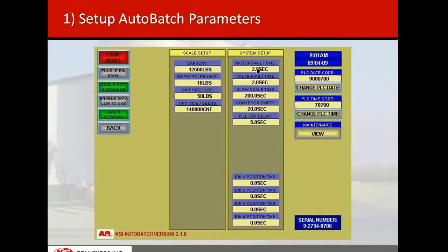On the right, we have some system setup parameters. Motor fault time is how many seconds we give the motor before it faults: 2 seconds. Valve is 2 seconds, and this would be for your air gates. The slow scale time is 200 seconds. This is how many seconds we give the scale to reach capacity, and if it has not filled in 200 seconds, we will alert the operator through the alarm light that something is obstructing the seed in your system. Maybe the bin ran empty or something like that.